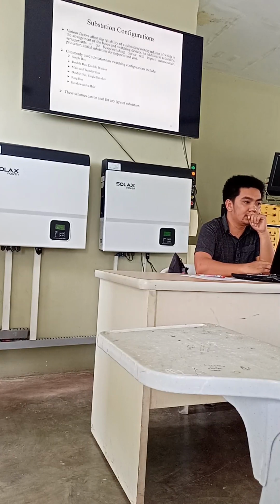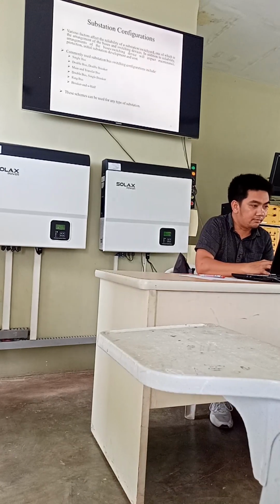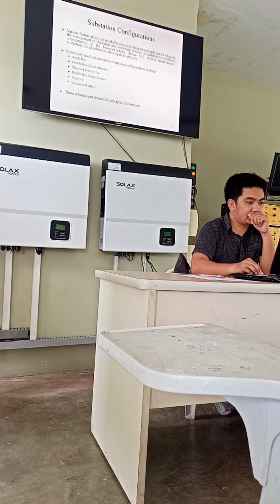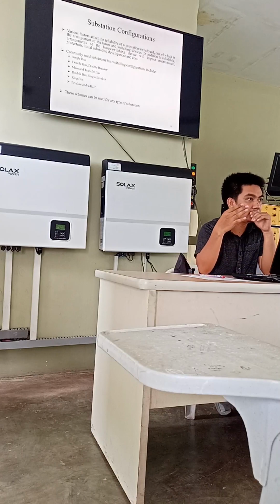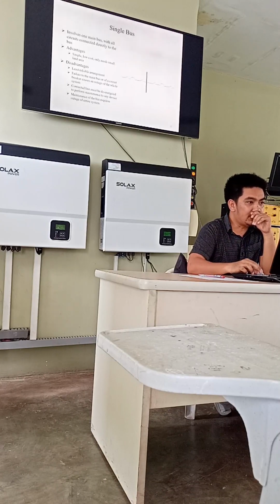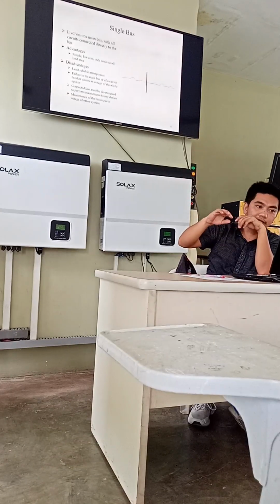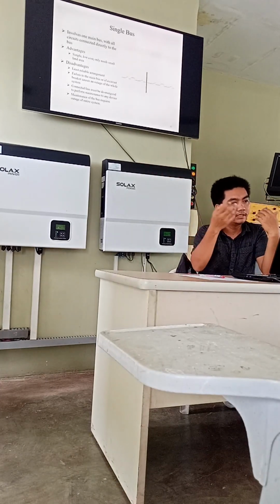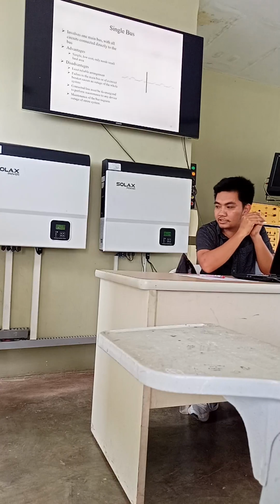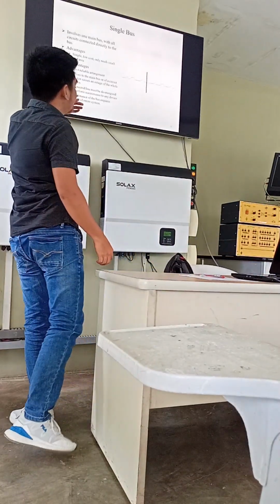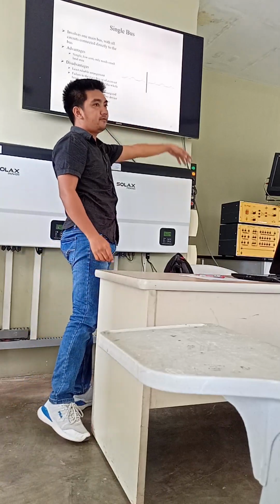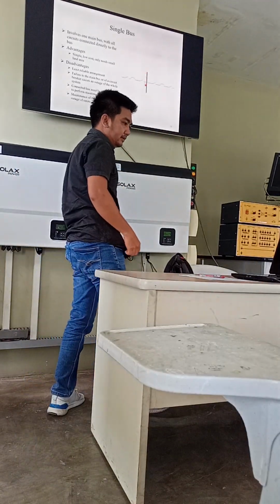These are the commonly used substations: single bus, double breaker, main and transfer bus, double bus, single breaker, ring bus, and the most common nowadays is the breaker and a half. These are the schemes that can be used to construct the substations. When you say a single bus, you have the common bus here in the center, and then the incoming circuit would be, let's say, this is a typical distribution substation. The incoming circuit from the subtrans level, and this one is for the primary feeders or primary line distribution.